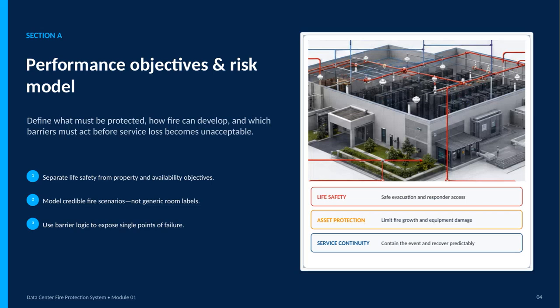This section establishes the foundation for the fire protection system: clear performance objectives and a realistic risk model. The first step is to define what must be protected, because not every objective is the same. Life safety comes first, with a focus on safe evacuation and reliable access for responders. Asset protection is related, but distinct. Its purpose is to limit fire growth and reduce damage to equipment. Service continuity goes further, asking whether the event can be contained and whether recovery can proceed predictably.